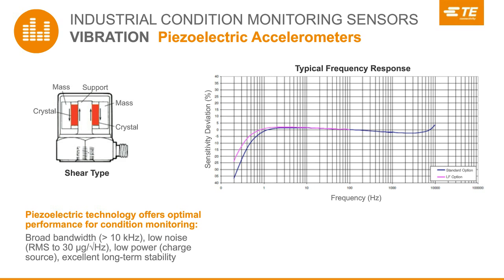Why do we prefer piezoelectric technology for condition monitoring accelerometers? We can easily achieve an operating bandwidth of over 10 kilohertz. We also obtain a very low electrical noise floor, particularly at high frequencies. The piezo sensing element requires no excitation signal. It's actually a source of charge or voltage. Therefore, piezoelectric accelerometers can operate using very low current or power. This makes them ideal for battery-powered systems. Finally, the sensing elements are very stable and don't change in properties over time. And this is critical when tracking changes in signal amplitude over the lifetime of a machine.